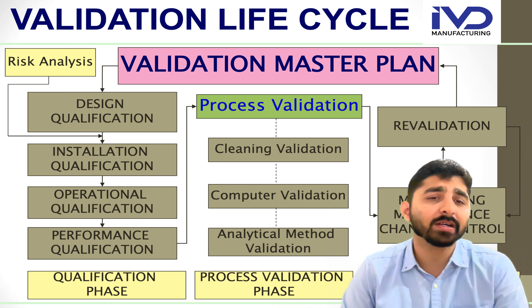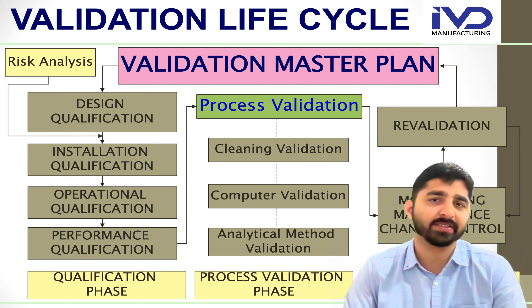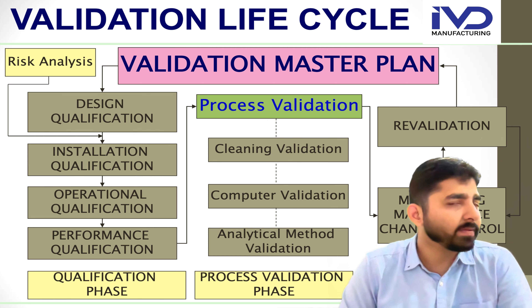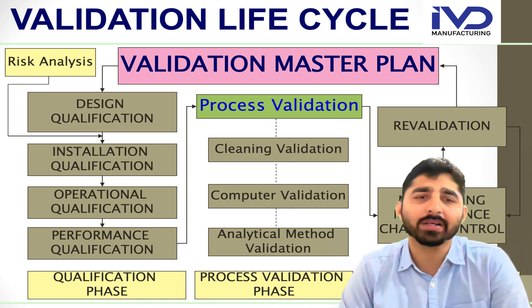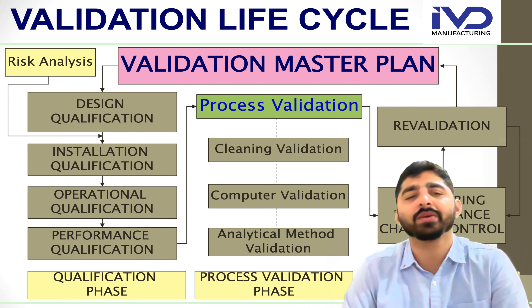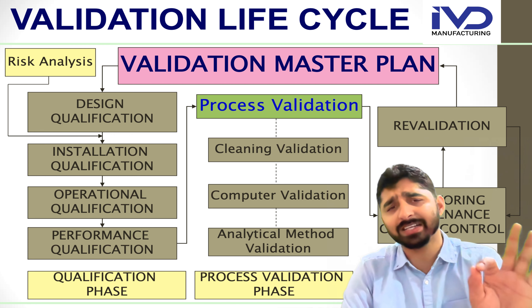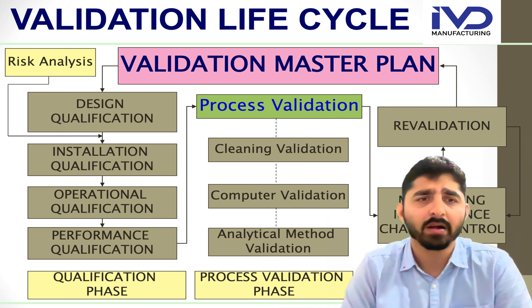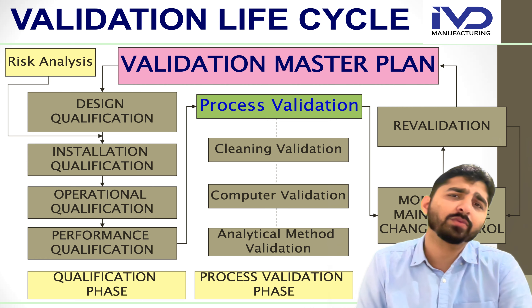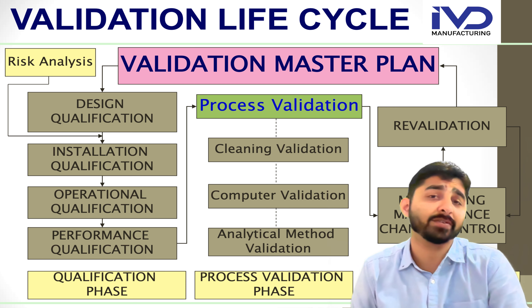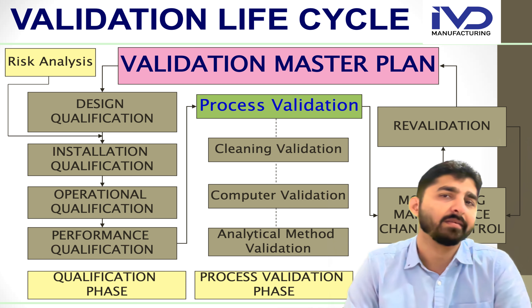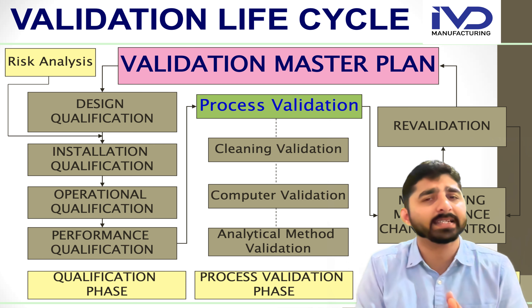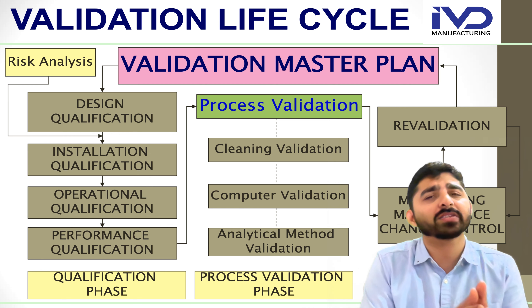Before setting up any facility, you go through the qualification phase where all instruments installed on the premises undergo the basic procedures: DQ, IQ, OQ, and PQ. I won't go into detail on each of those, but all four types of qualification need to be governed by a risk analysis procedure to minimize risk. Once a company finishes the qualification phase, it moves into the process validation phase.